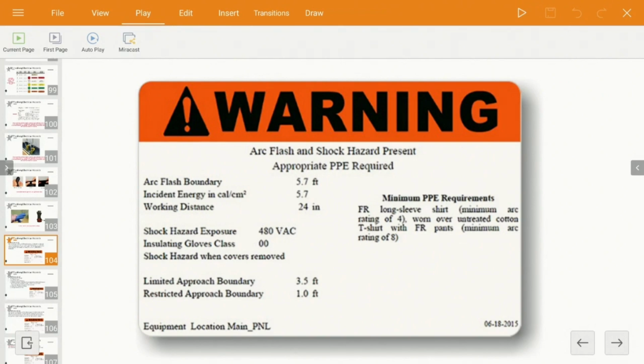Keep in mind that arc flash boundary is calculated at a distance where if somebody that's not suited up in their arc flash PPE is standing right there at your boundary, this says they will only get a 2nd degree body burn. That's bad, right? What's that unprotected person going to do if they get burned up over most of their body? Huh? Well, if they live. Or if they don't, what's their family going to do? One call, that's all. They're going to sue you and your employer, everybody involved.